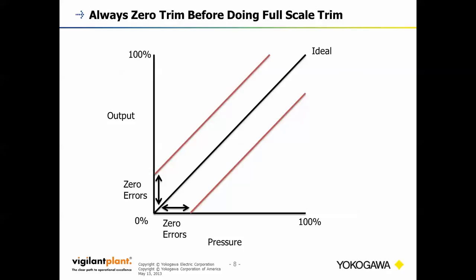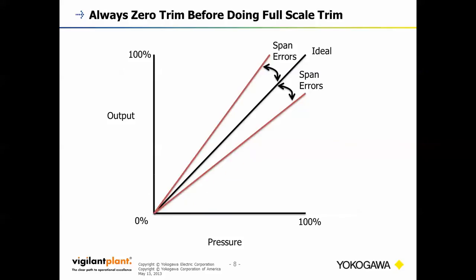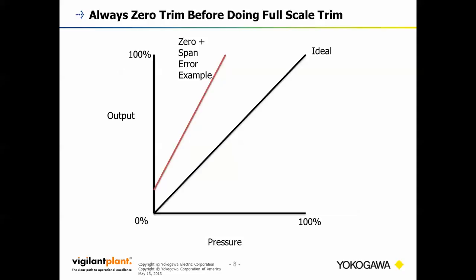So we can have 0 errors, which will affect the offset of the linear line. If you think back to algebra, y equals mx plus b, that would be your b value. And then we can have span errors, which affect the slope of your line. That would be the m portion of y equals mx plus b. So if you have a transmitter that's out of tolerance, with both 0 and span errors, we're going to go over why you want to 0 trim before doing a full scale trim, and what the consequences could be if you don't.